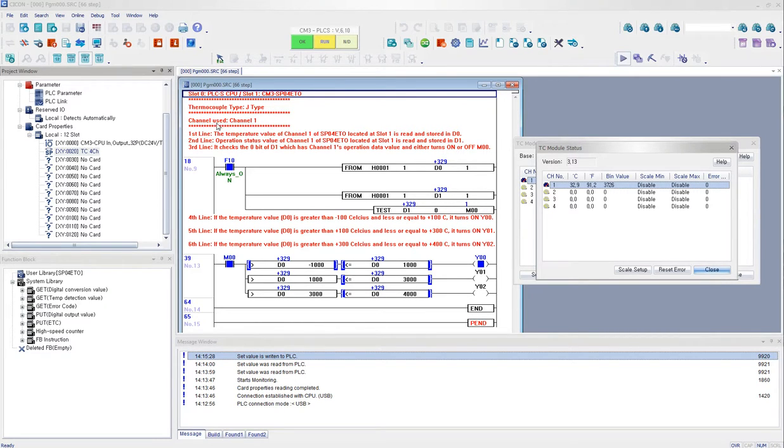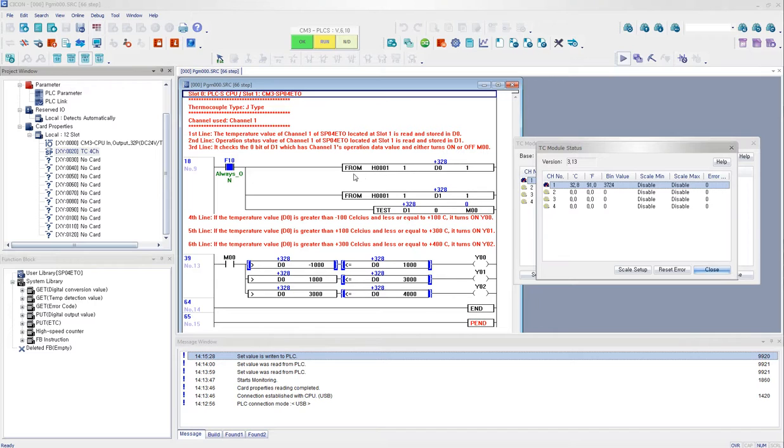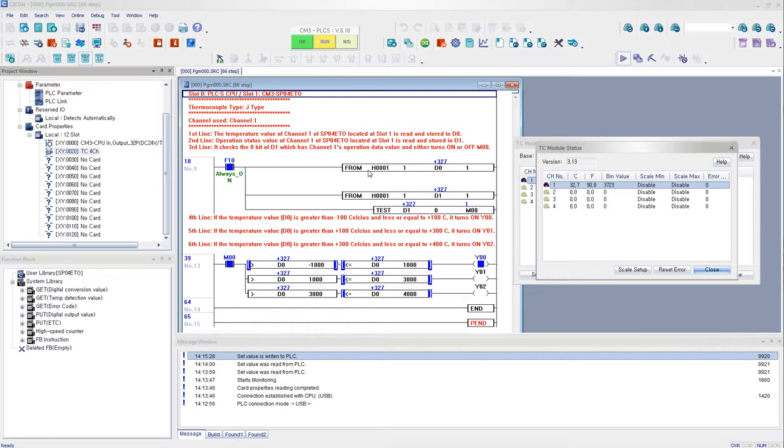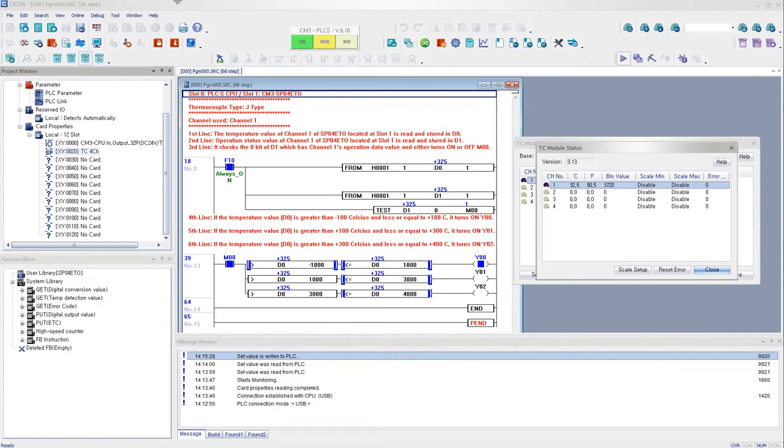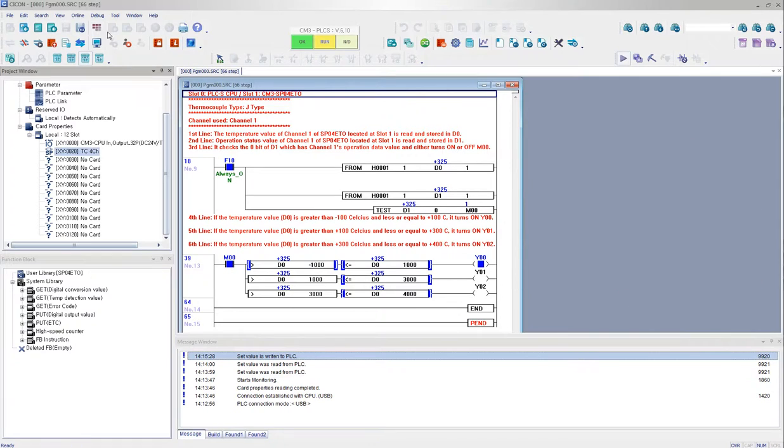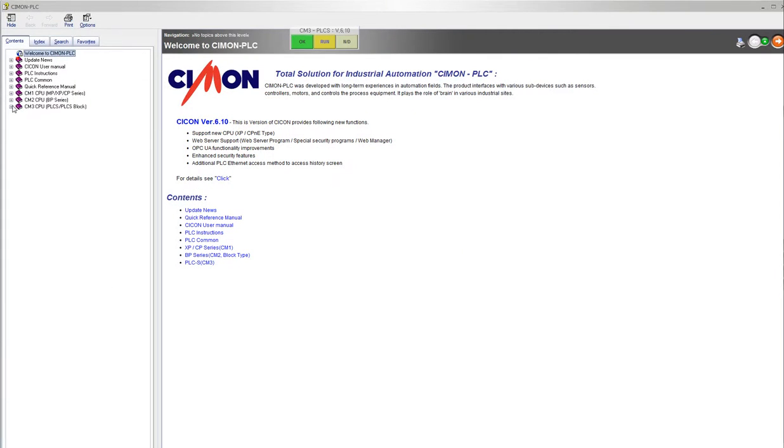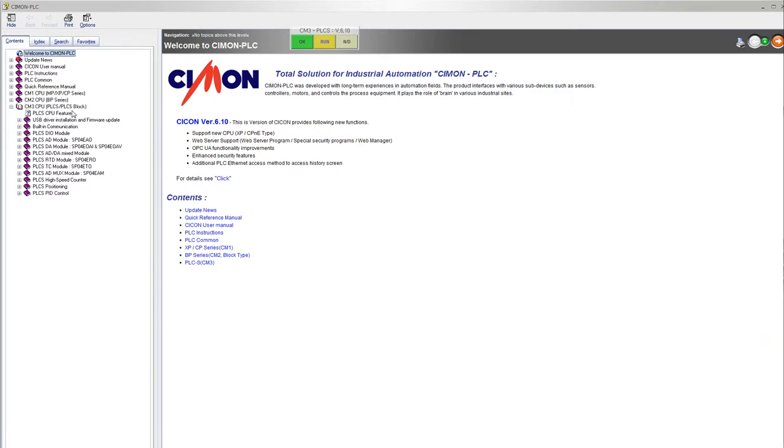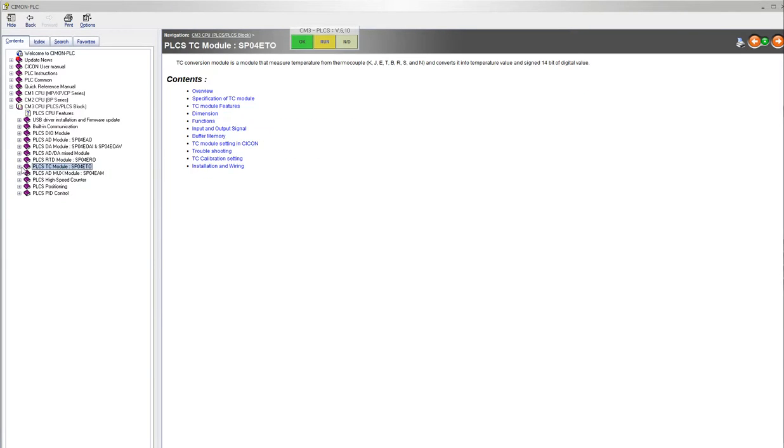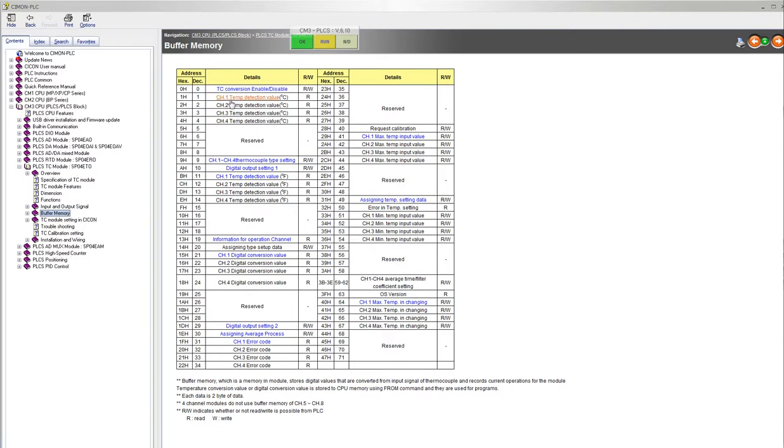And the channel that I'm using is channel 1. So the first line shows that I'm using the FROM command to read the data, the channel 1 temperature data. And it is according to the buffer memory. So I go to help, and then I click on CM3. I go to SP04ETO. I click on buffer memory over here. And it tells me that the decimal number 1 is to bring the data of the channel 1 temperature detection value in Celsius.